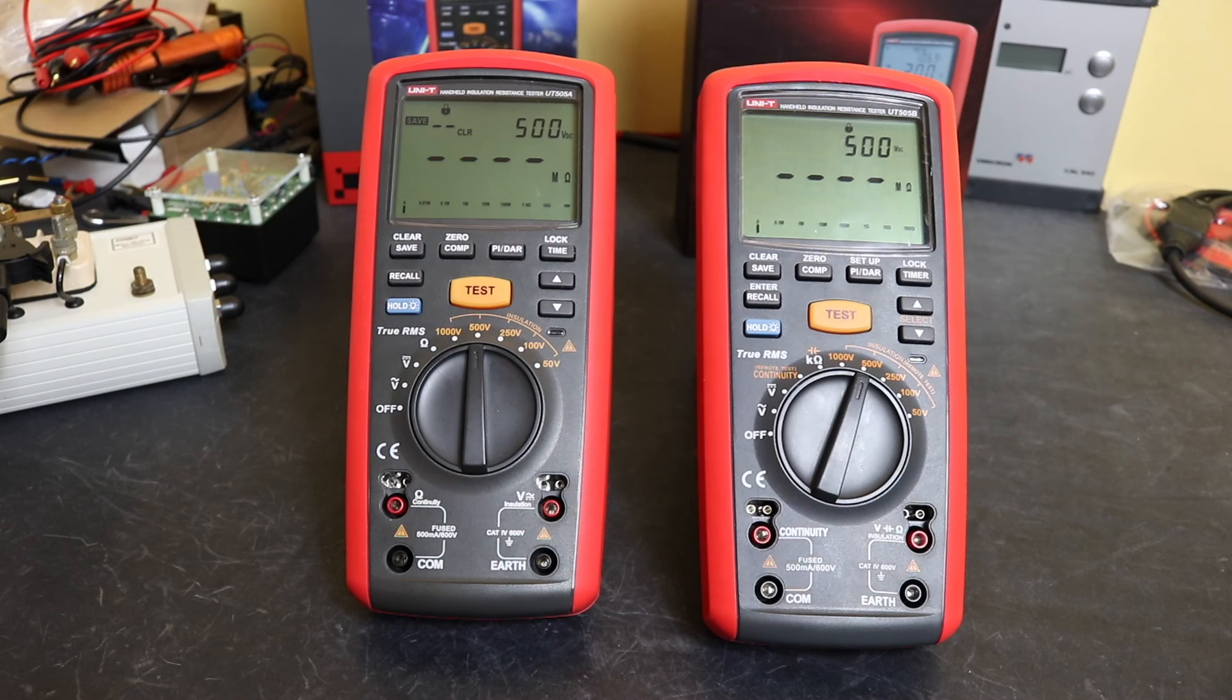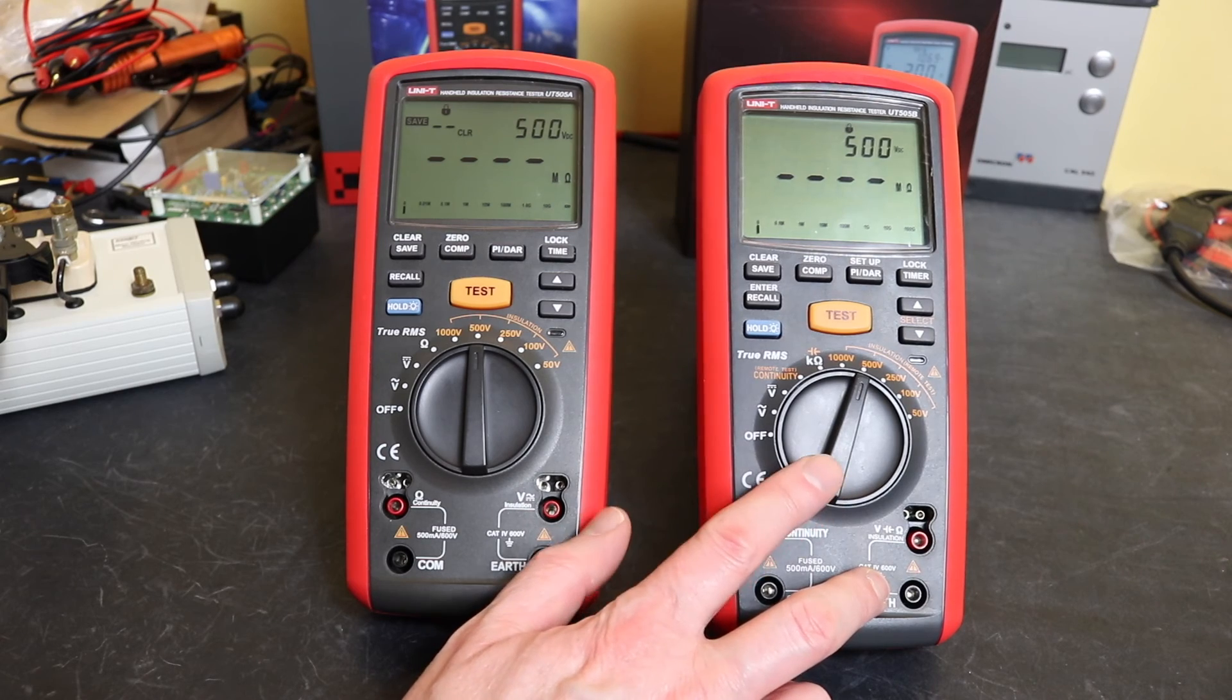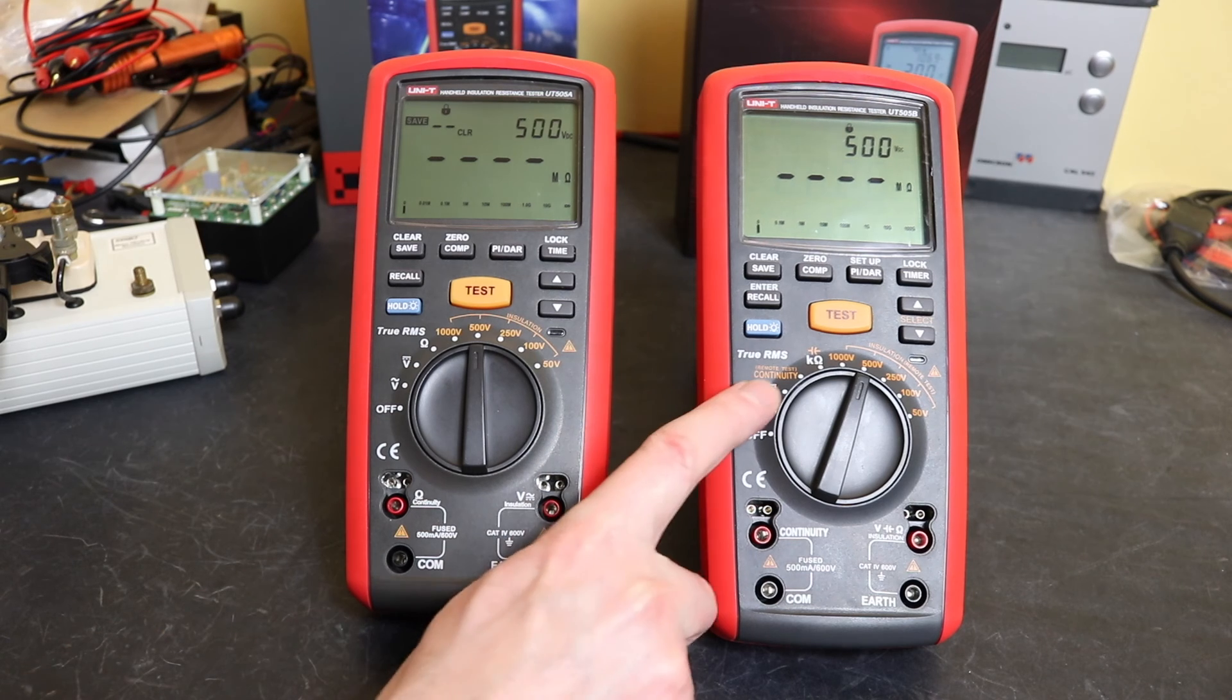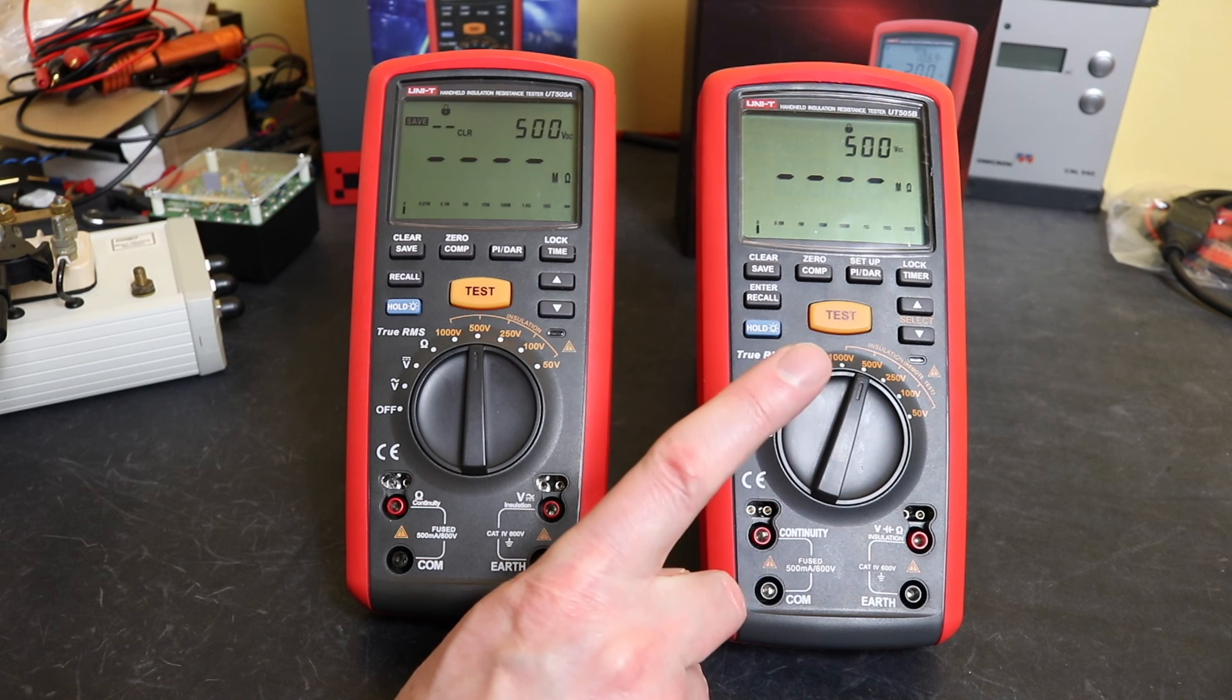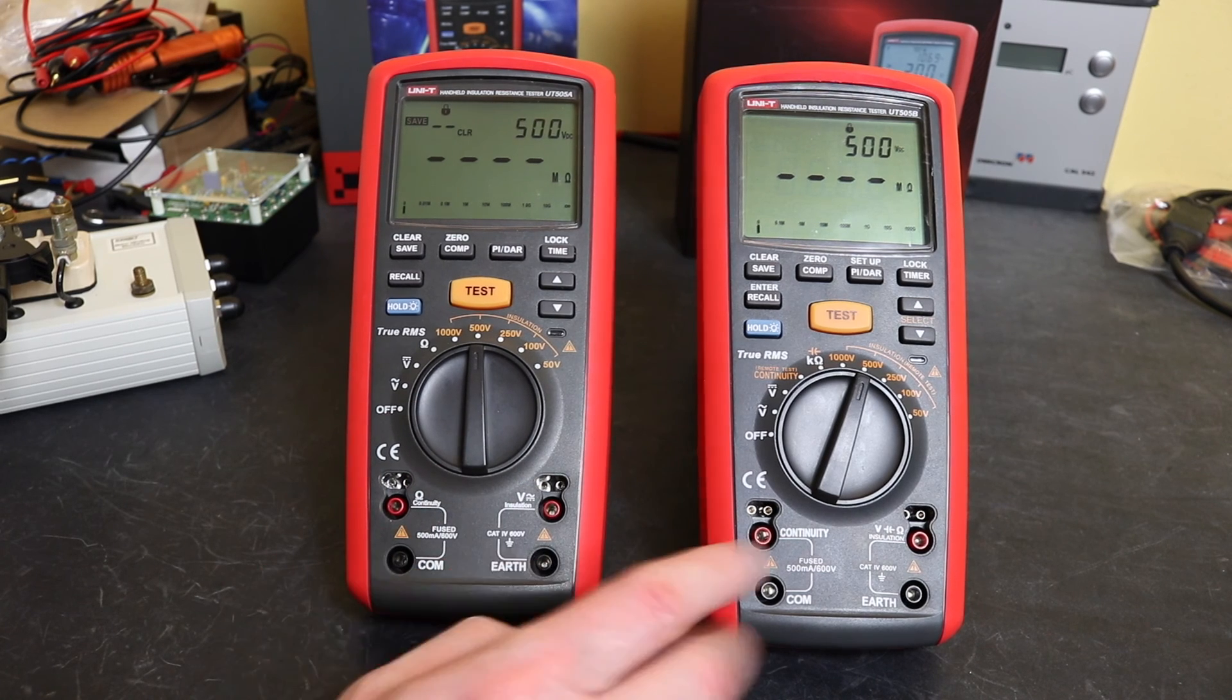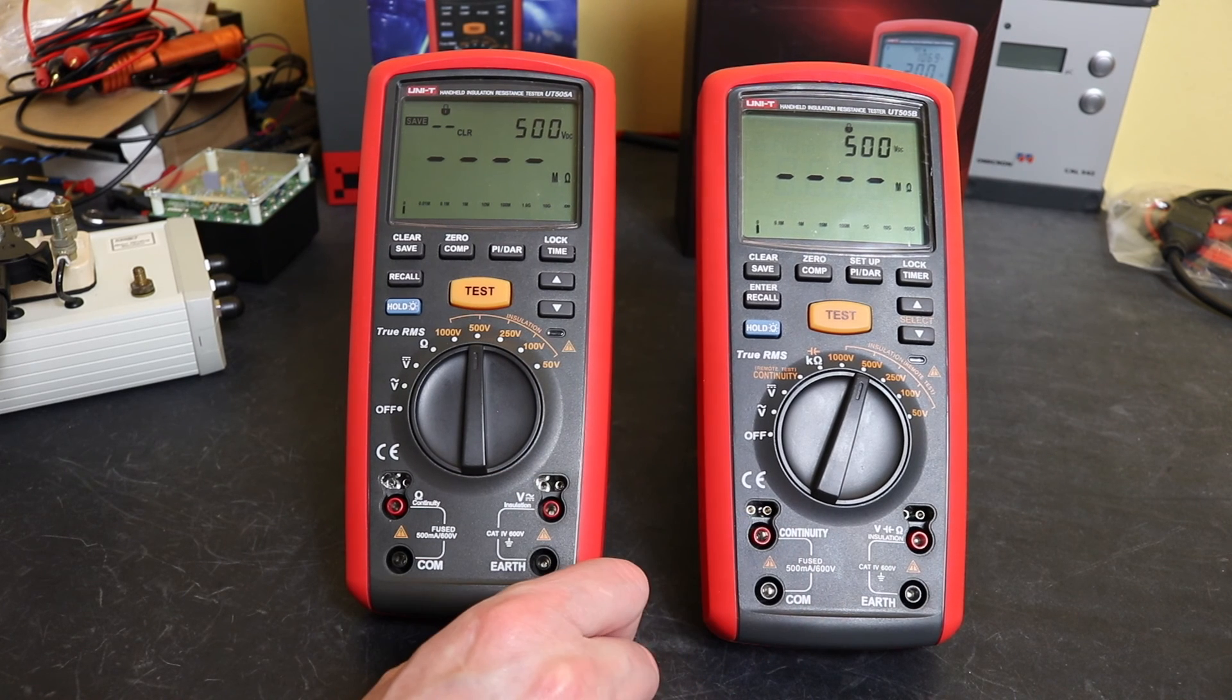So that's the two instruments there. For me personally, I would go down the UT505B route because it gives me much more extended range with the insulation test function, and I prefer the way the PI and DAR do operate. There is the issue with the continuity that you can sort out with a capacitor as I showed in a previous video. Probably what I should do is break these both open at some point and see if there's a difference between the two circuits, because it's strange that this doesn't have any issue with the continuity function when I've tested stuff. I've only seen it on this instrument here.